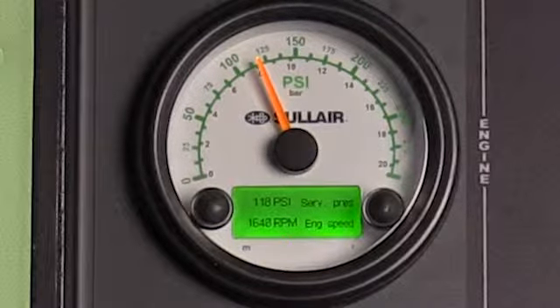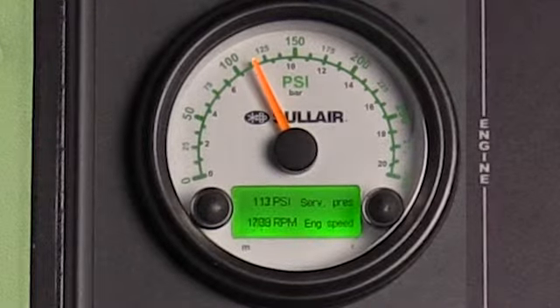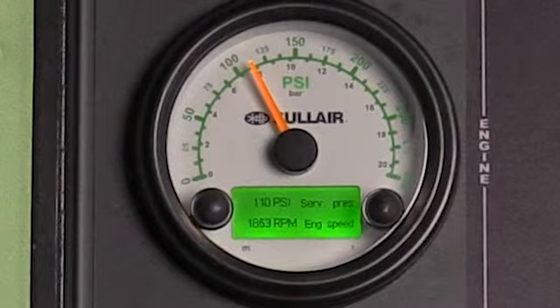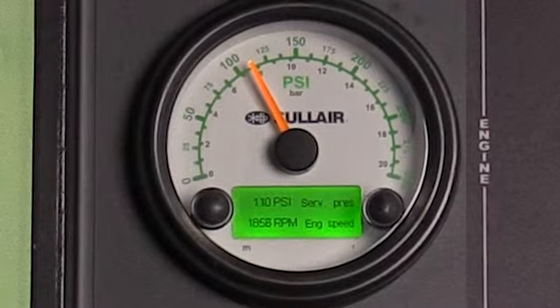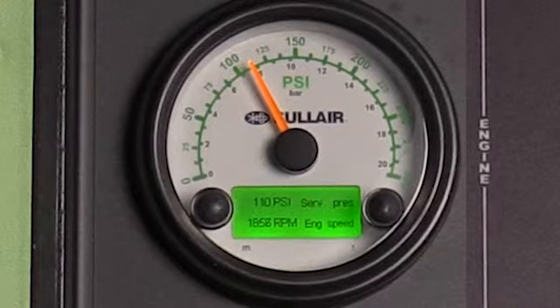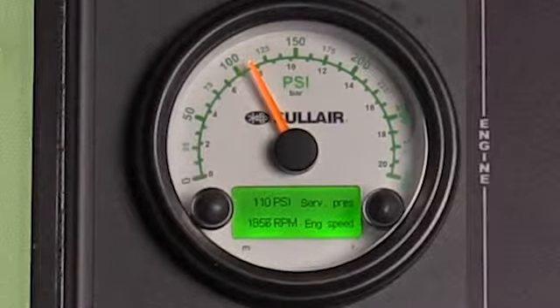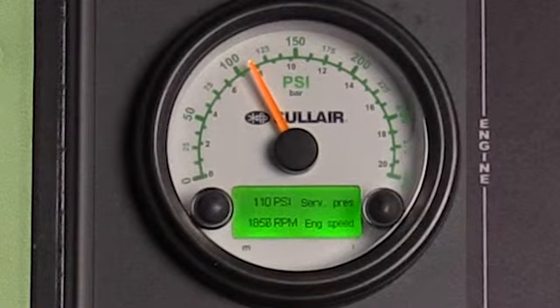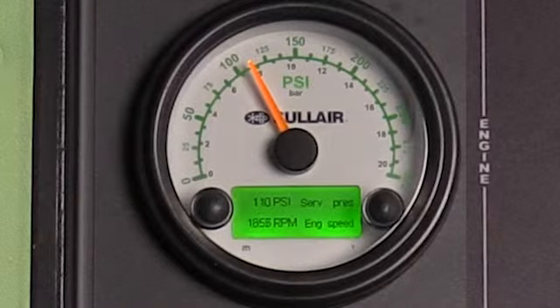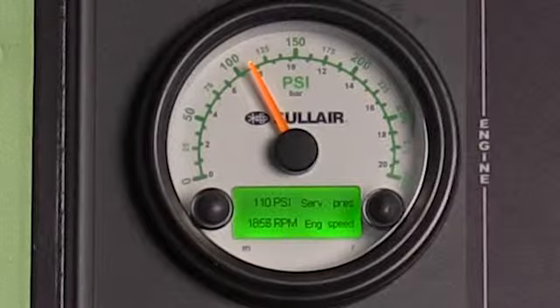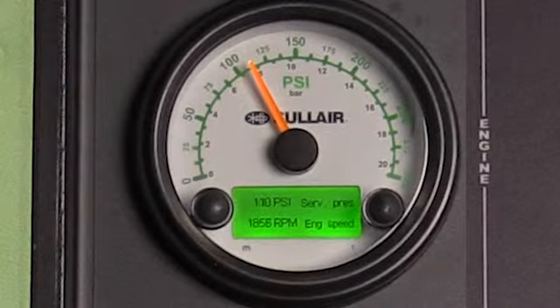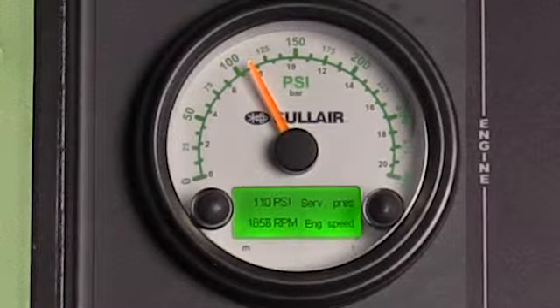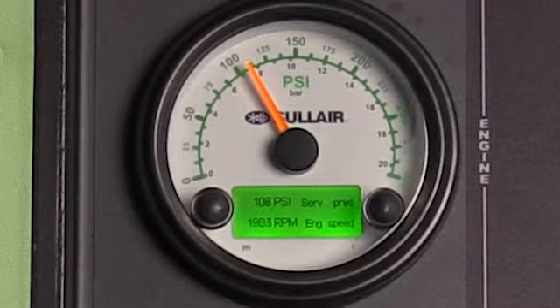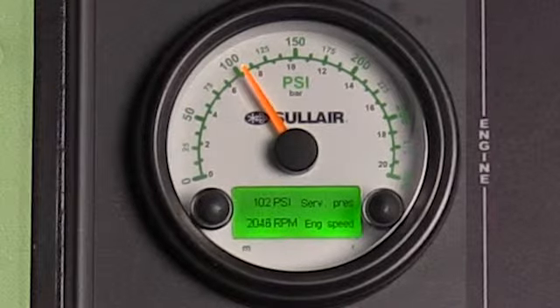Here we are in the modulated state. With the ball valve only open partially, this is simulating again a partial load on the compressor. This is going to put us somewhere between minimum and maximum RPM and the inlet somewhere between fully open and fully closed. You just have to remember that modulation resides in between the full unload setting and the full load setting. Here we're going to demonstrate the transition between modulation to loaded.